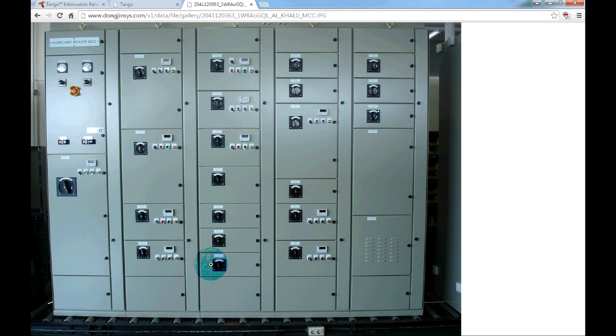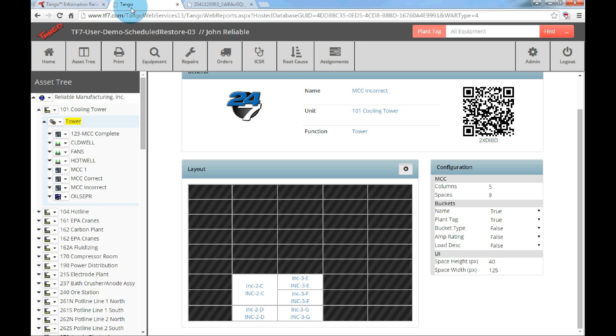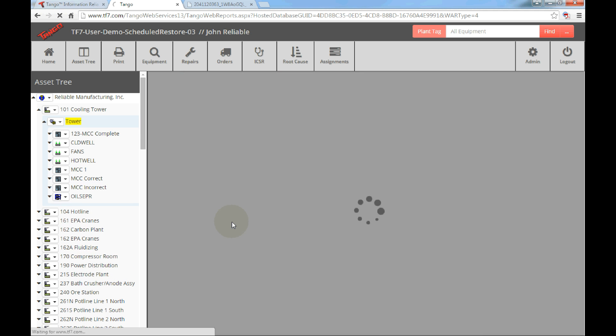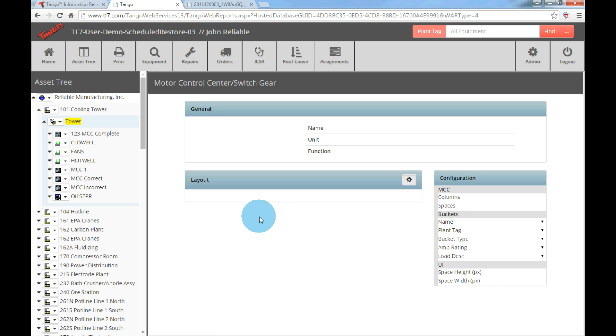In order to make the layout accurate, we will need more spaces to make the two panels equal. So in order to make this work, in this case, we can see that the two buckets in column two takes one and a half small buckets of space. So halving the size of the smallest bucket will allow us to properly size the two larger buckets in column two. Therefore, the smallest bucket takes up two spaces, and the total spaces will equal 18 instead of nine. Now with 18 spaces, we can size the two buckets correctly compared to the smaller buckets in column three. Here's what the layout looks like with the proper 18 spaces.